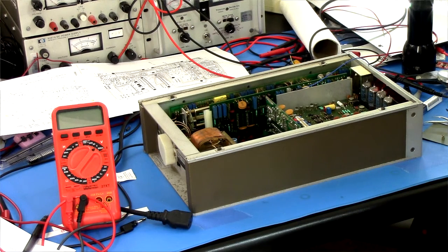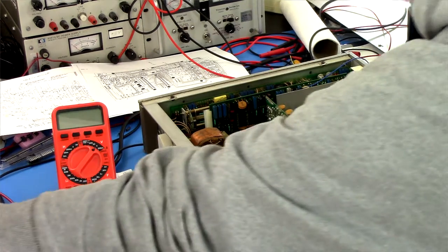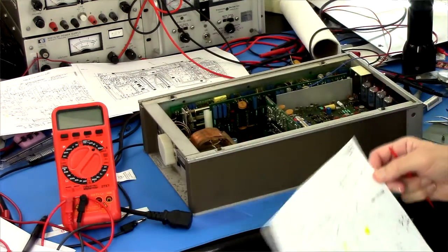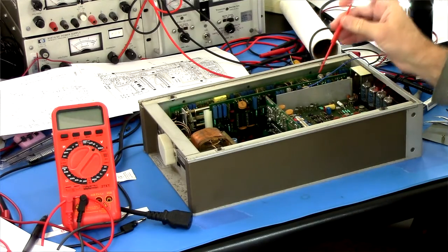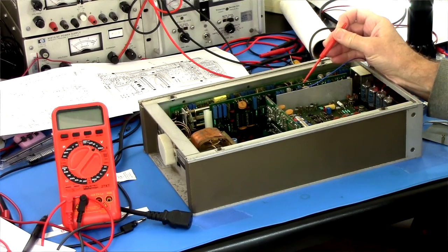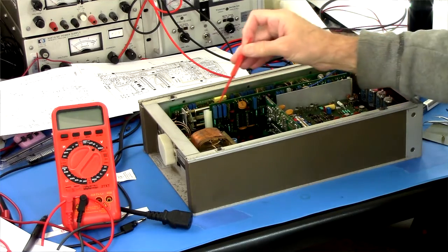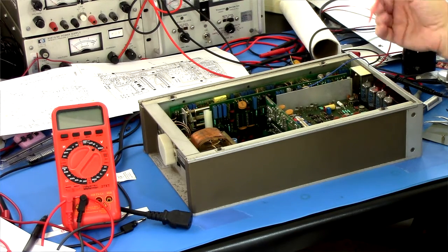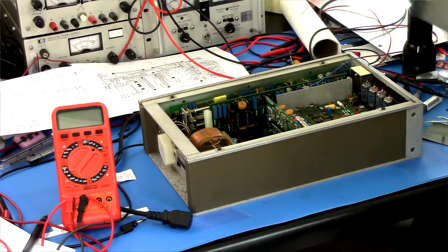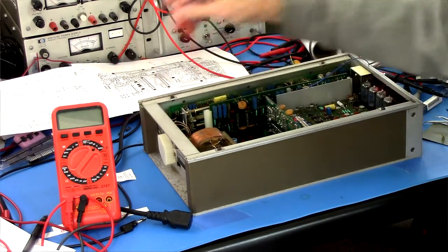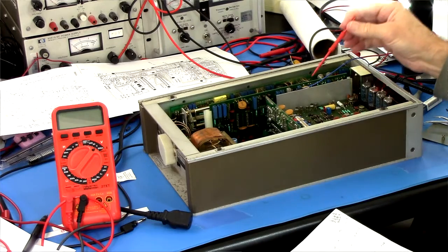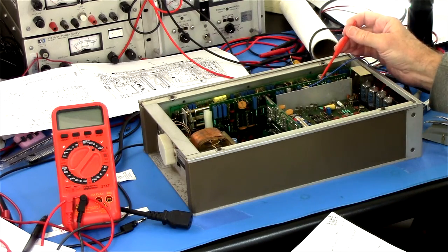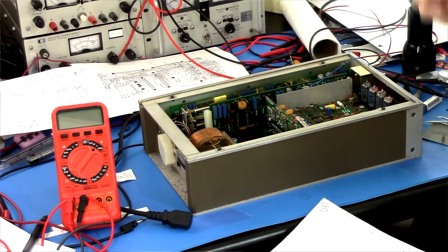It's time to take another look at the Keithley 171, see if we can work through the latest problem, and maybe that'll be the last one. Who knows? So, to review, we've apparently tracked the problem down to the analog amplifier board, which is this one here. Because if I pull that out, then I can put a voltage in where that was providing the voltage, and I'll get reasonable readings.